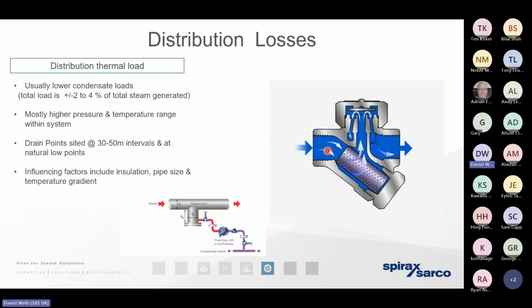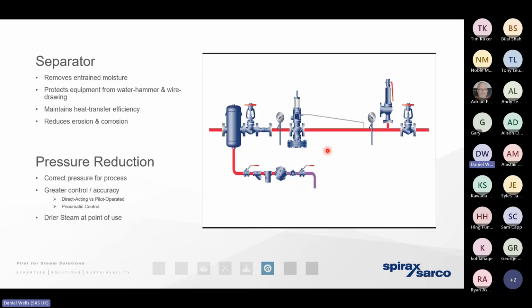So we've mentioned those steam traps. We need to ensure that we've engineered the correct type and the correct size of steam trap to get the condensate away from the distribution pipework. It's going to be a relatively small mass, but it's going to exist at a high temperature and therefore at a high pressure, which means it does have a value if we can get as much of that condensate, not only out of the infrastructure, but back to the boiler house where we can reuse it as well. So keeping those steam traps in mind to ensure that they're sized and selected correctly is critical.